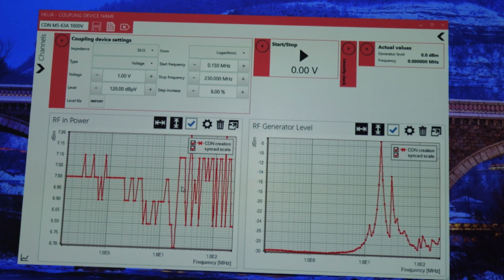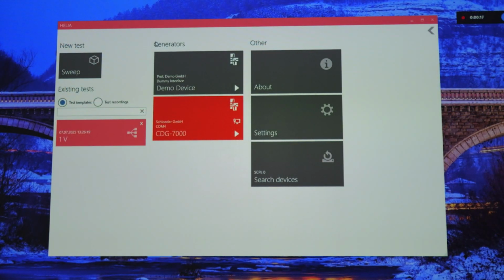Now that our CDG 7000 finished its calibrated sweep, you're going to have this correction factor from the signal generator, so you're going to know how much power it needs to drive, and then we're going to use this when we actually run a test. I'm going to make sure this is saved, and then we're going to go back. Now that I'm back in my main menu, instead of going into the settings to set the test level, I'm going to go to New Test and Sweep.